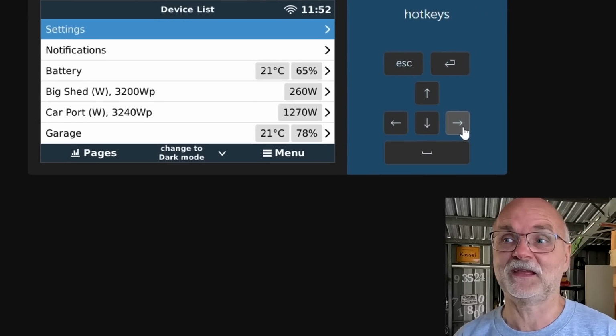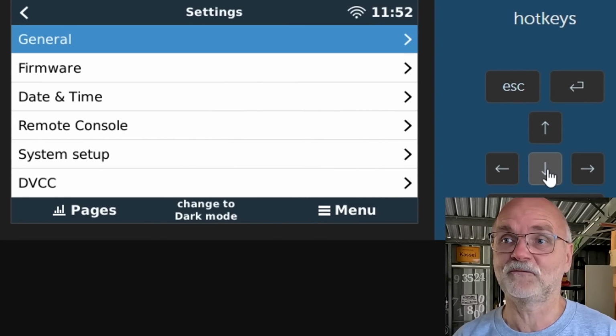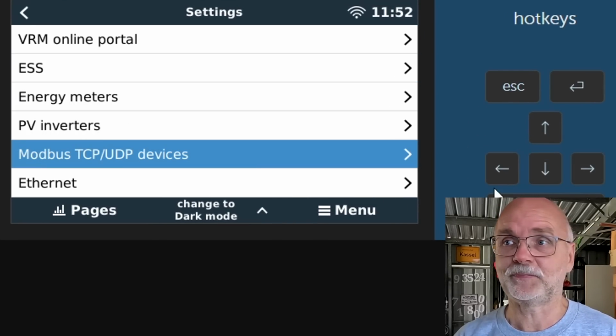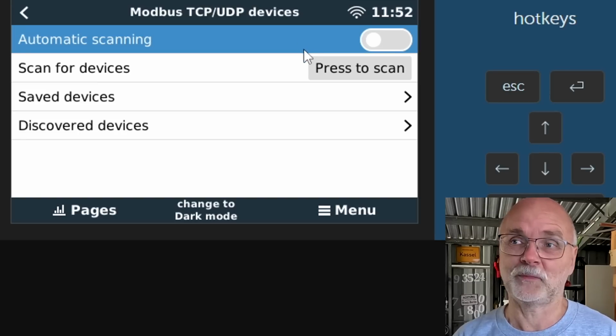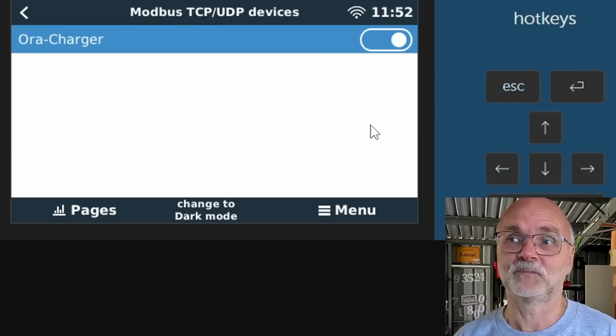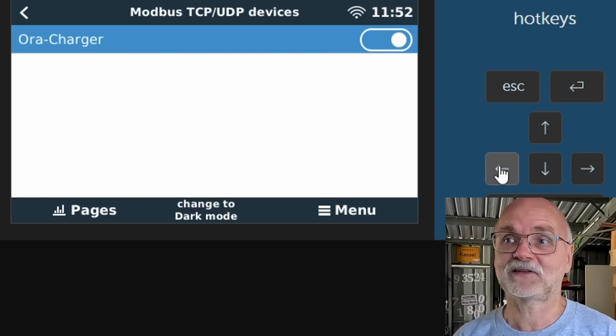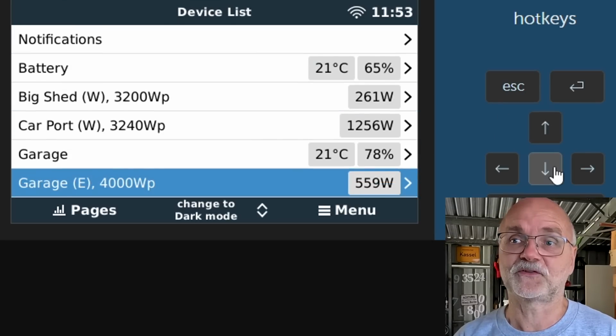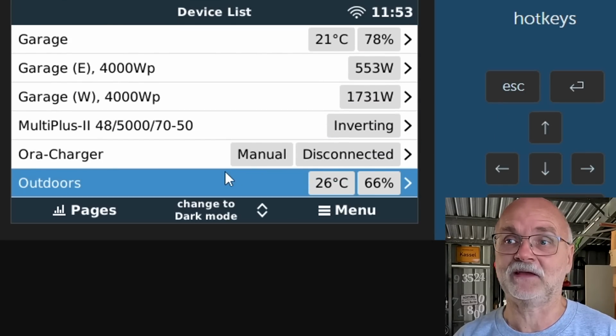You need to go into your remote console settings in Victron, go to Modbus TCP devices, and either do an automatic scan, or - I've just turned on the Ora-Charger, it was already there but turned off, so I activated it. Afterwards it shows up here in the list as the charger.